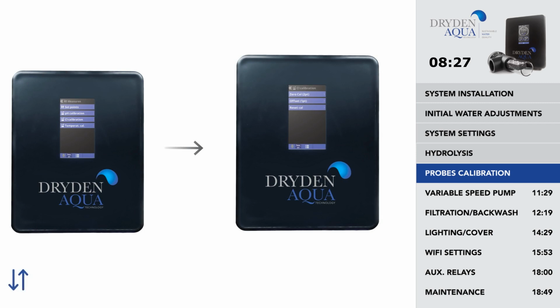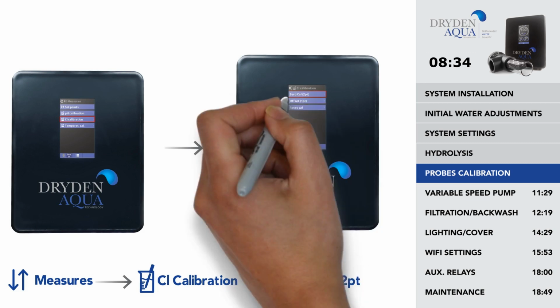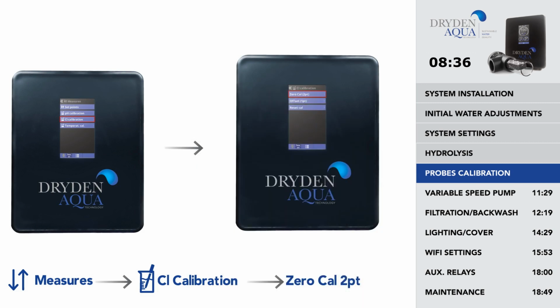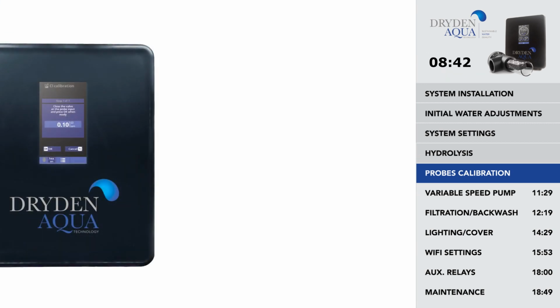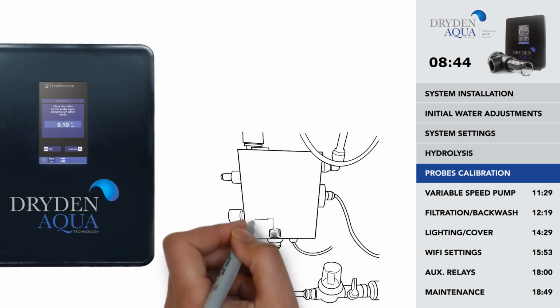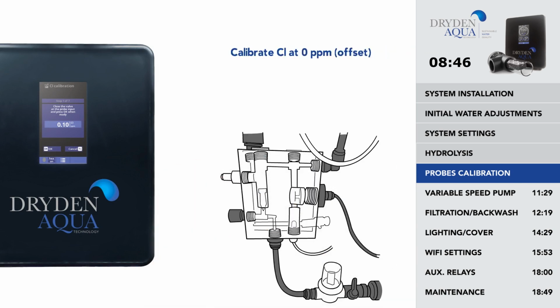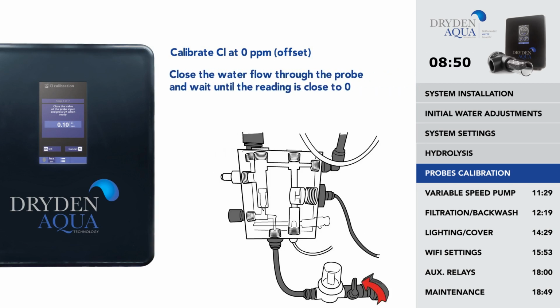Go to the Measures menu and press on Chlorine Calibration. It is important to always do the first calibration with buffer using a photometer and DPD1 tabs. Follow the instructions in 7 steps that appear on the display. First, calibrate free chlorine at 0 ppm. Close the water flow going through the probe and wait for 1 to 10 minutes until the reading is close to 0 and press OK.